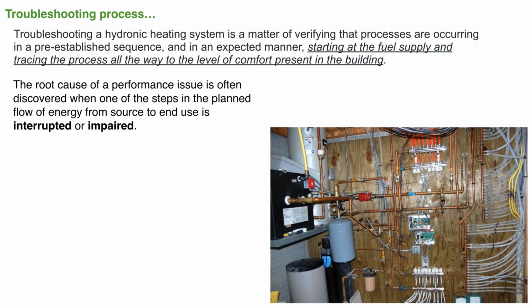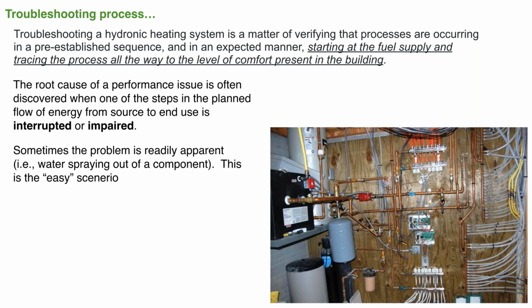So as you move step by step through the troubleshooting procedure, maybe at step 4, a contact in a relay is supposed to shut and turn on a circulator. Well, the circulator isn't on. Maybe that contact is broken or the device that operates that contact is broken. So that's the idea, step by step. And obviously, sometimes the problem is very apparent. You walk into a mechanical room, you see water spraying out of a boiler. Well, it's pretty obvious that's a problem. It may not be the only problem with the system, but obviously water spraying out of a boiler or smoke coming out of an electrical control is something you've got to deal with quickly. And I put down, that's kind of the easy scenario. It's obvious what at least that initial problem is.